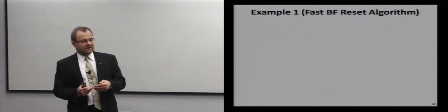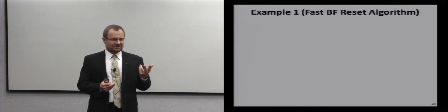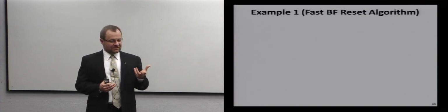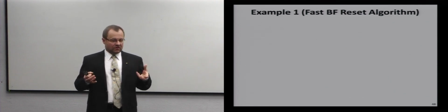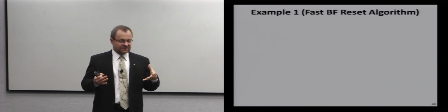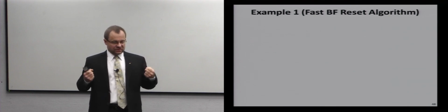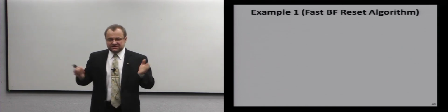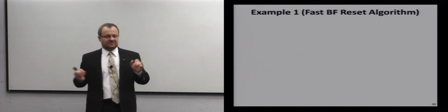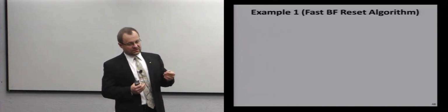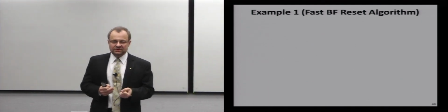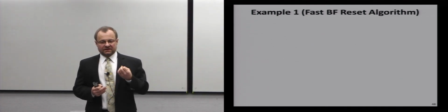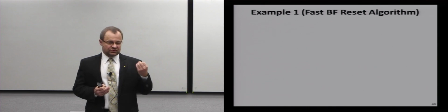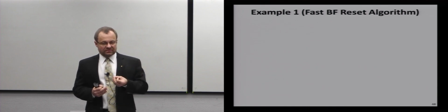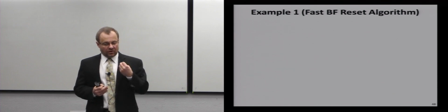Breaker is too big and too expensive to put two of them. So we put one of them, we give it two coils to trip the mechanism with two different trip coils, but it's just one breaker. If it fails, that's it. So breaker failure protection is monitoring if a breaker was ordered to trip, did it really trip? If it didn't, the breaker failure protection operates.